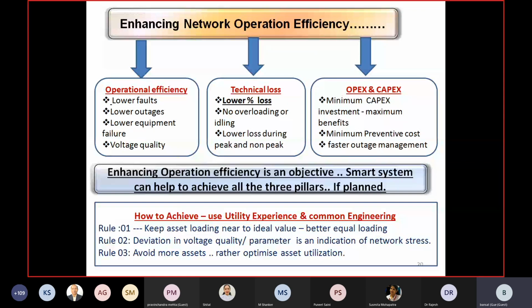My formula, my methodology, my philosophy is simple: keep the asset near the ideal value so that we have equal loading. If there is a deviation in voltage quality and other parameters, it indicates network stress. Rather than keep adding assets where they are stressed, or just revamping or adding new assets, replan: identify which assets are overloaded and which are underloaded, and transfer the load from overloaded to underloaded, so that you have balancing and the best operational efficiency. So I have to do this.